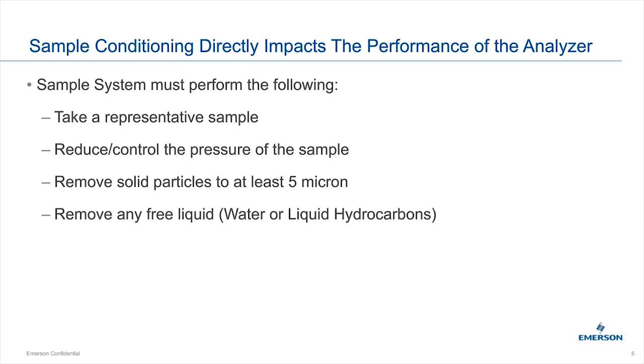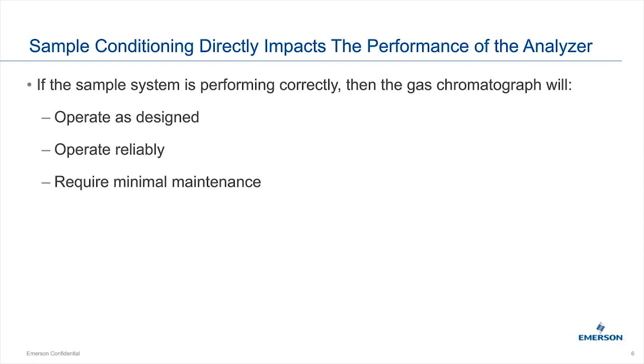Fifth, if you accomplish the above four items, maintaining the composition of the sample becomes much easier — though you still have to be careful about hydrocarbon dropout when changing pressure, which can affect temperature. If we get the sample handling system right, the GC will operate as designed, operate reliably, and require minimal maintenance.